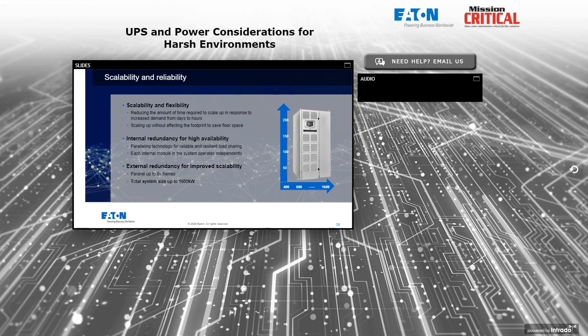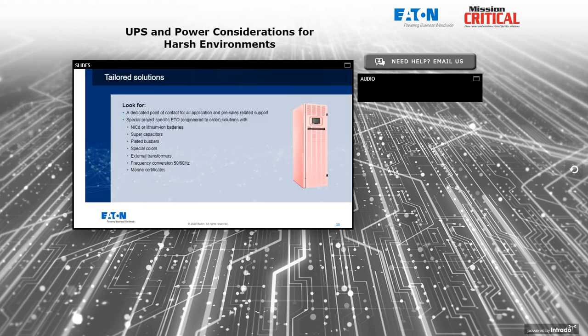So a product that scales in kilowatt capacity, both vertically by stacking smaller UPSs in a bigger box and horizontally by putting these larger boxes side by side and connecting their outputs in parallel, again, for increased capacity or redundancy. Tailored solution. Client says, I need to buy a lot of these, but I need them to have certain features. In this case, this client wanted pink paint. All of the power infrastructure in their application was painted this color, and it actually made it safe and easier for the maintenance staff and the operations staff to work with. So those kind of things should be on the table, at least as an option for these types of UPSs.